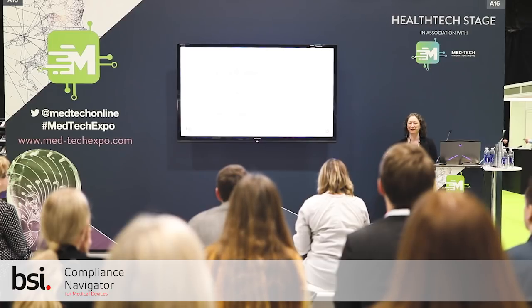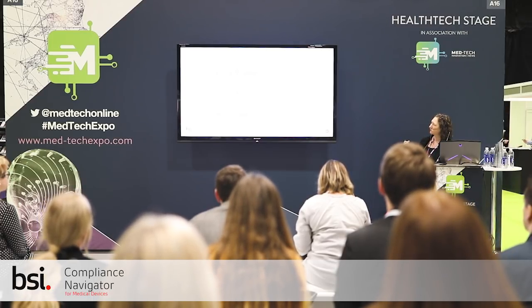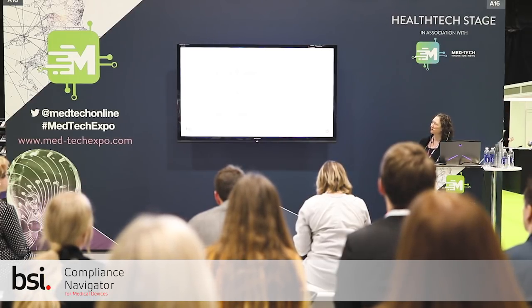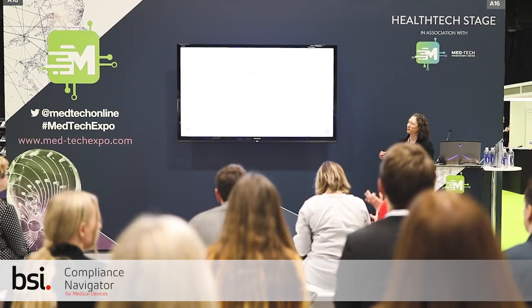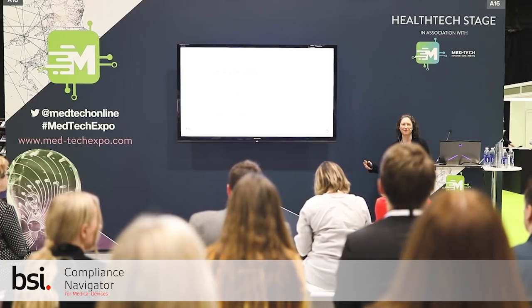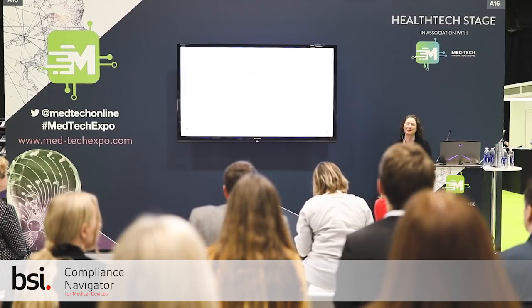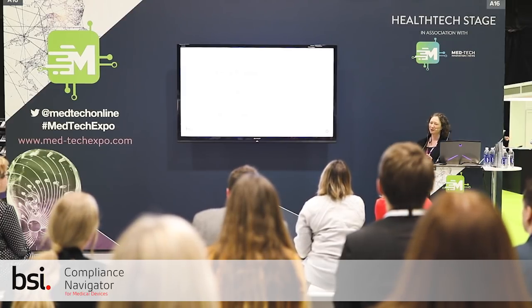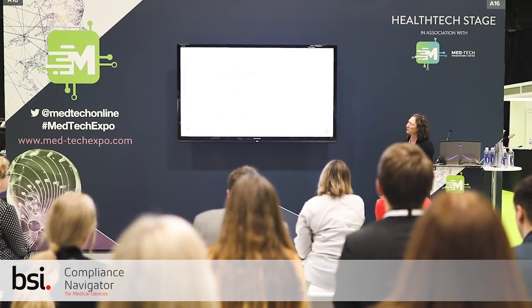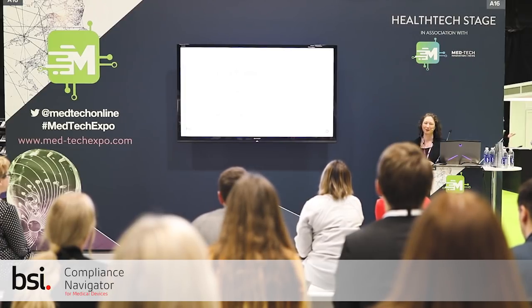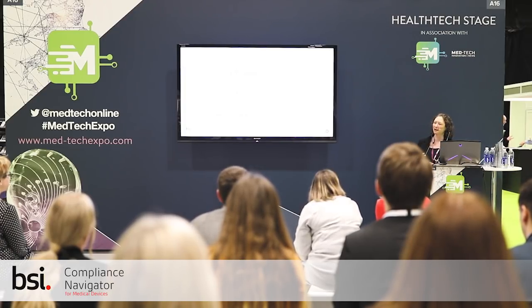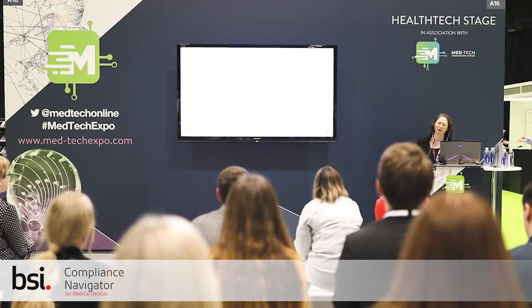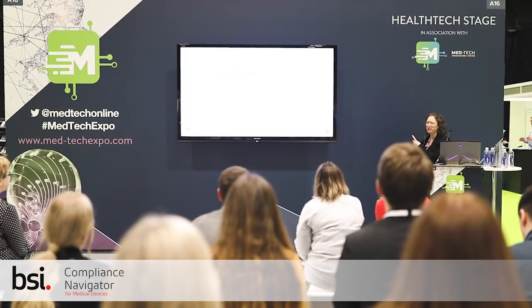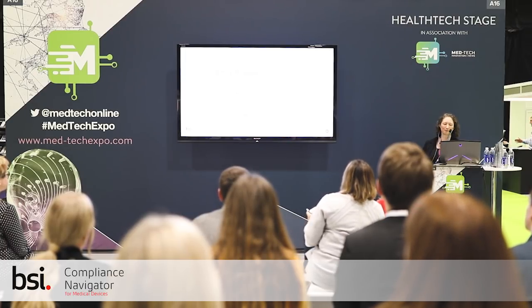That's not always very well understood, but now it starts to say a methodologically sound, systematic and planned process. So you can't just get to the end of your device and go, well, I'm just going to put these papers together. You need to have defined how you gathered the data, you need to have planned how you gathered the data, and you need to have a procedure to do that. So it's a lot more detailed about what's required. Many manufacturers are already doing this.